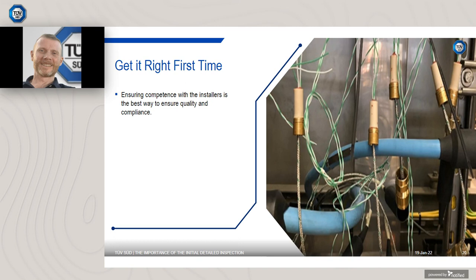Ensuring competence with installers is the best way to ensure quality and compliance. Ensuring competency with installation personnel is as critical as carrying out inspections. Once again, in this photo, cable type and gland selection are an issue. The installation was found during a pre-FAT EX inspection, and again, had to be rectified at supplier cost, thus saving time and money on the project.